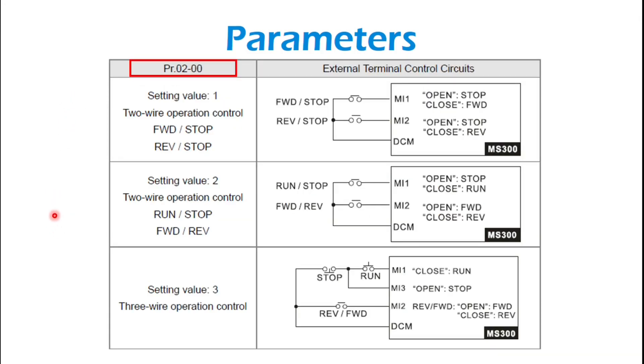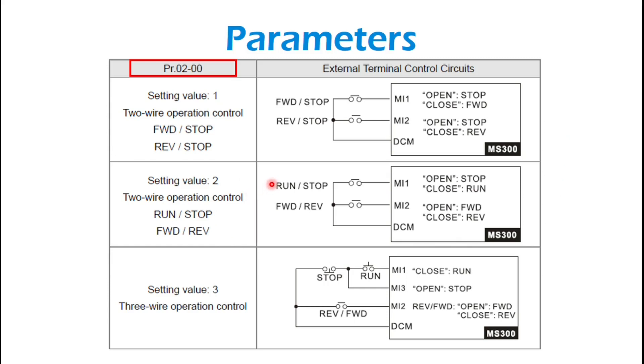And then 0200, these are the same diagrams from the earlier slide, just blown up so you can see it a little bit better. Also wanted to mention setting value 2. So this is another two-wire operation control where you're doing run-stop from MI1, and then your direction forward-reverse is on MI2 instead of forward-stop-reverse-stop. So just a small difference there.